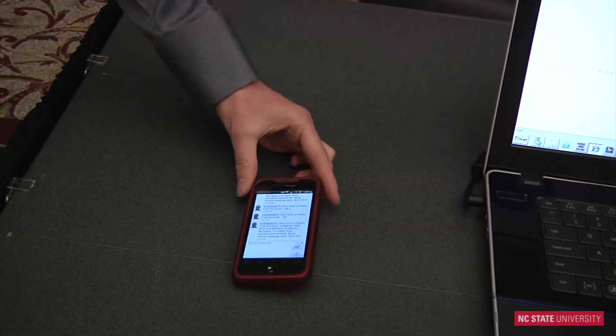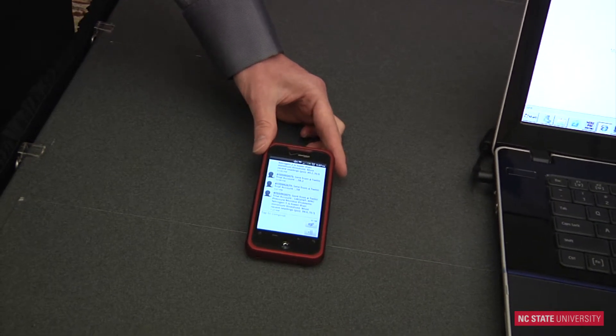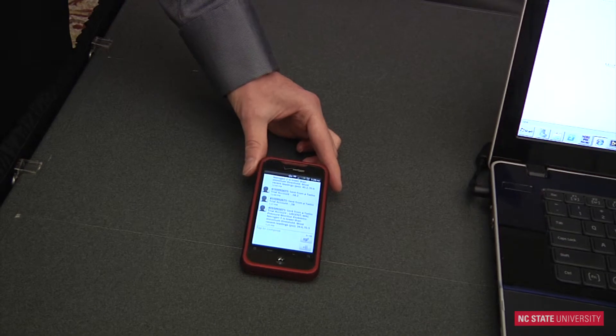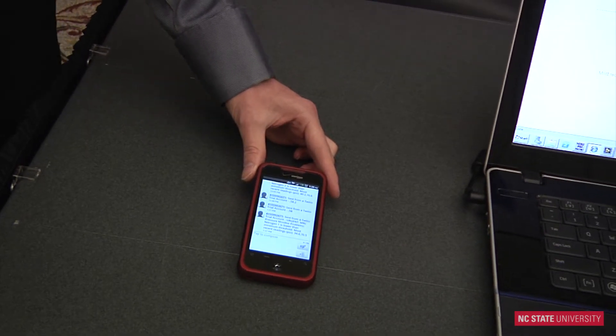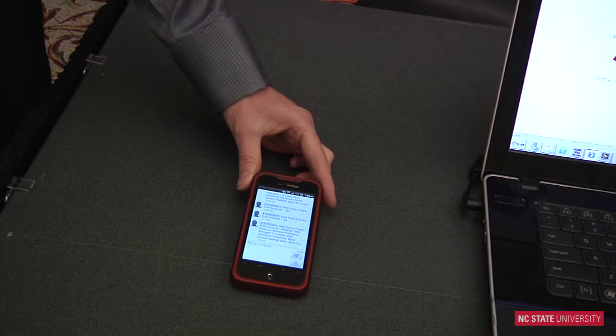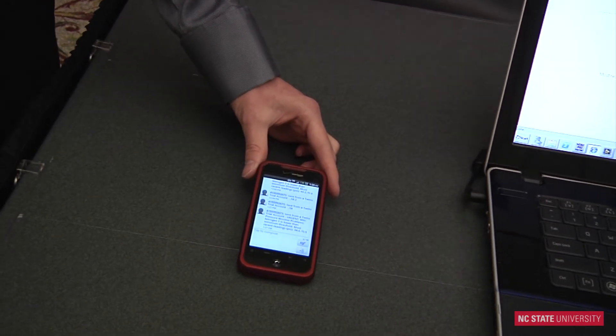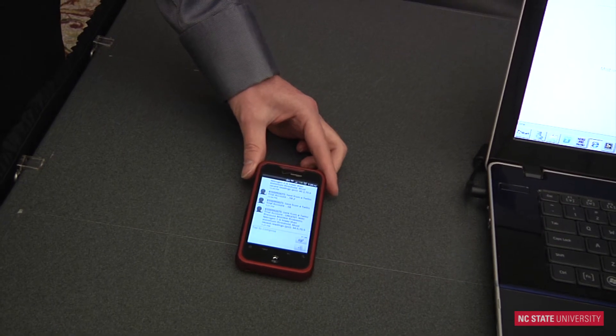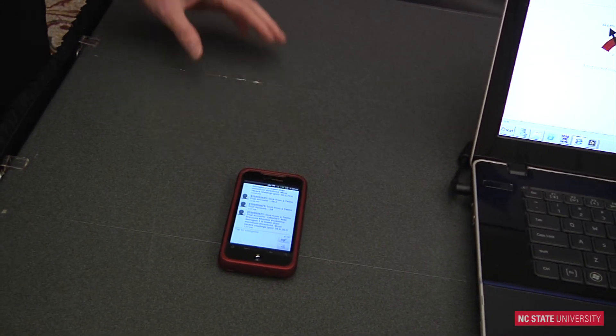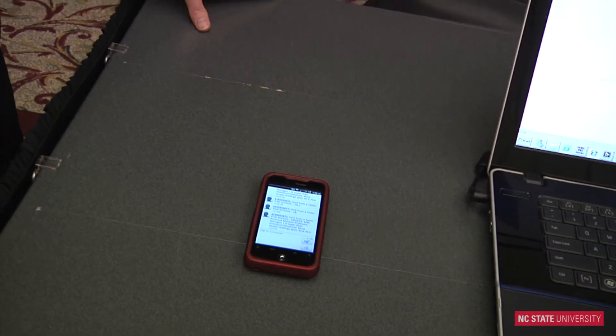So basically what happens for the text alert: it will show which tank is below the threshold or above the threshold. And if there's more than one, they'll say that tank 1 is below threshold, tank 2 is below threshold. Then they'll give you the current values of each individual tank at the time that this alert came in. After an alert is sent, it will wait 15 minutes unless someone goes in and manually resets before it sends another alert.